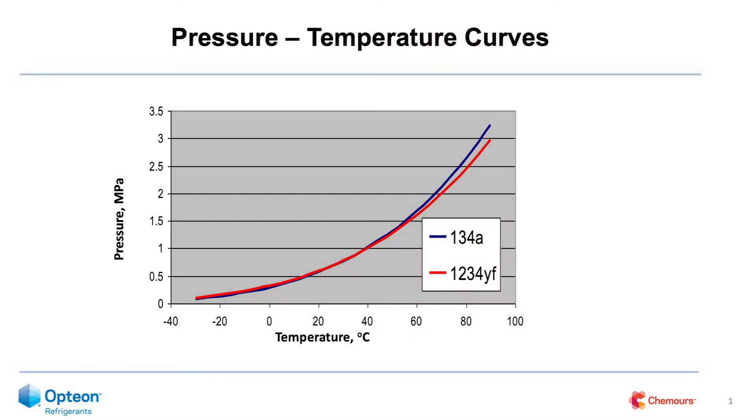R513A looks a lot like R134a if you look at its physical properties. I'm going to put up a chart of the pressure-temperature curve of R1234yf and R134a, and you can see how closely those lines lie on top of each other. When we make a mixture of the two, it's going to have very similar pressure-temperature properties, and in fact all the properties are very similar when you're looking at R513A compared to R134a.